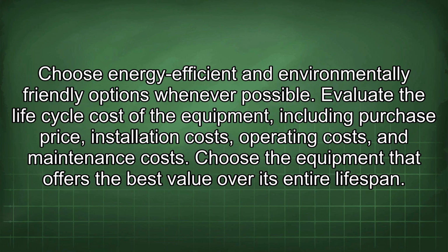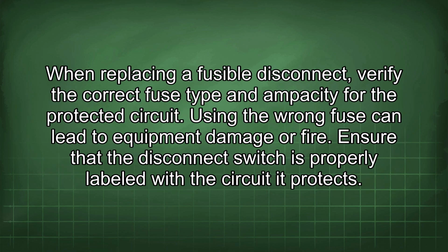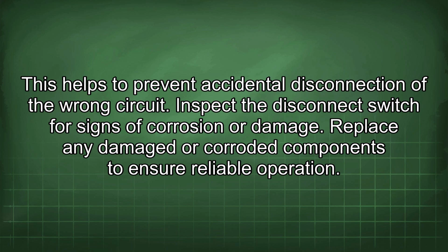Evaluate the life cycle cost of the equipment, including purchase price, installation costs, operating costs, and maintenance costs. Choose the equipment that offers the best value over its entire lifespan. When replacing a fusible disconnect, verify the correct fuse type and ampacity for the protected circuit. Using the wrong fuse can lead to equipment damage or fire. Ensure that the disconnect switch is properly labeled with the circuit it protects. This helps to prevent accidental disconnection of the wrong circuit.